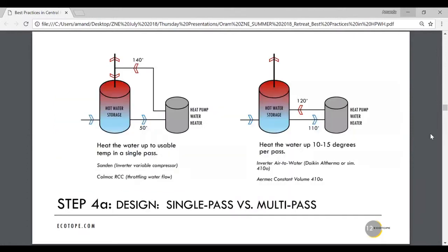The next piece in this approach is to understand your design, or hone in on one. There are two ways to heat hot water with the technology out there now: single pass or multi-pass. A single pass device takes 50-degree water and heats it up to a usable 140 degrees in one pass. A multi-pass is more like a boiler indirect, heating 10 degrees on each pass to bring the whole thing up. This is really important to understand, because with single pass you can bring 50-degree water into your heat pump—that's the sweet spot for heat pumps. So the game is to set your heat pumps up in single pass so you're always bringing in the coldest water possible. That's your efficiency gain.